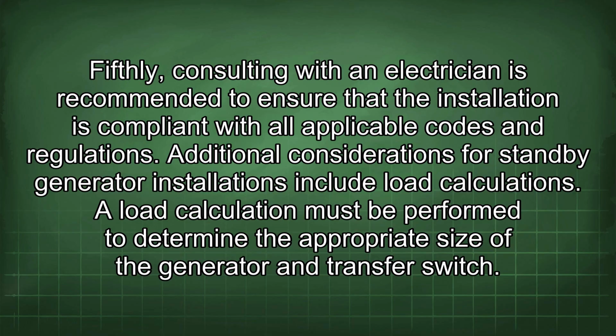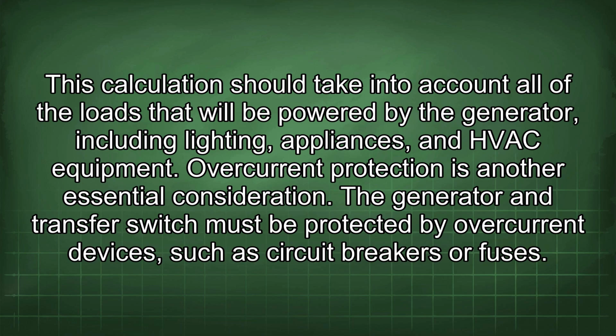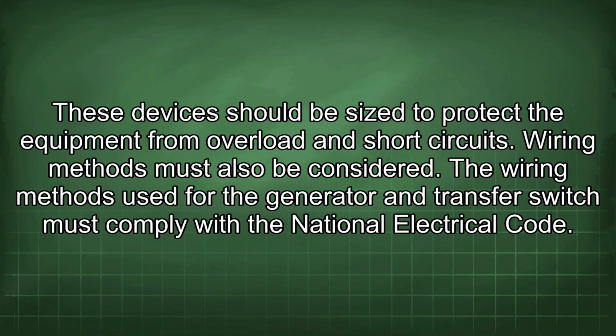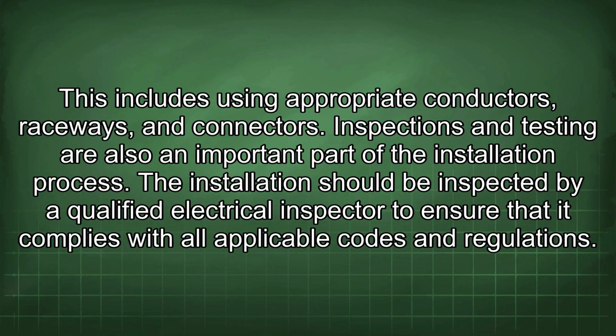Additional considerations for standby generator installations include load calculations. A load calculation must be performed to determine the appropriate size of the generator and transfer switch. This calculation should take into account all of the loads that will be powered by the generator, including lighting, appliances, and HVAC equipment. Overcurrent protection is another essential consideration. The generator and transfer switch must be protected by overcurrent devices, such as circuit breakers or fuses. These devices should be sized to protect the equipment from overload and short circuits. Wiring methods must also be considered. The wiring methods used for the generator and transfer switch must comply with the National Electrical Code. This includes using appropriate conductors, raceways, and connectors.